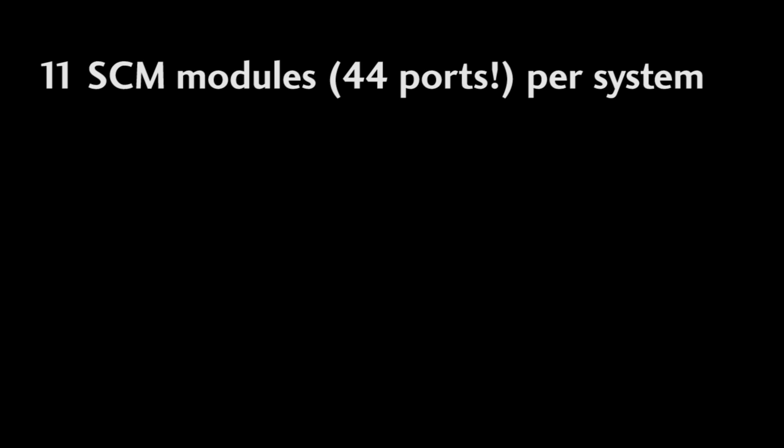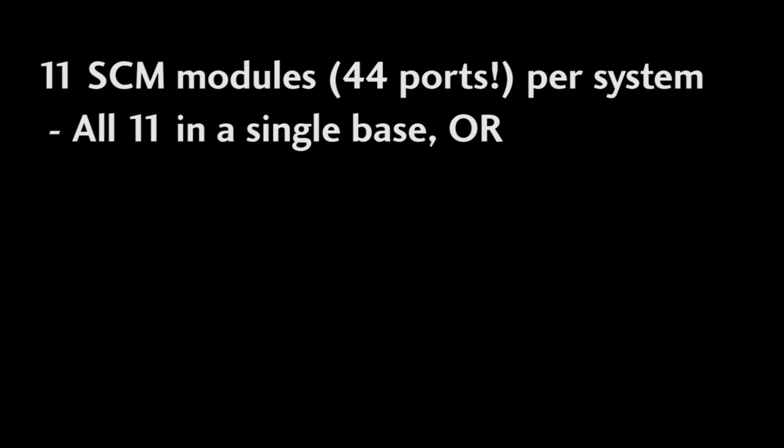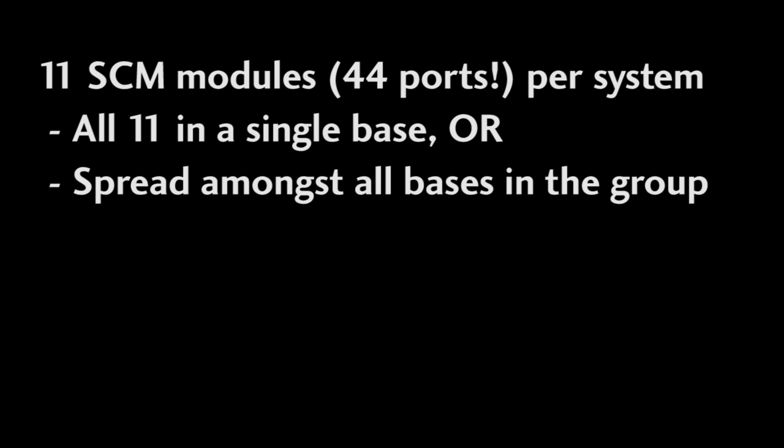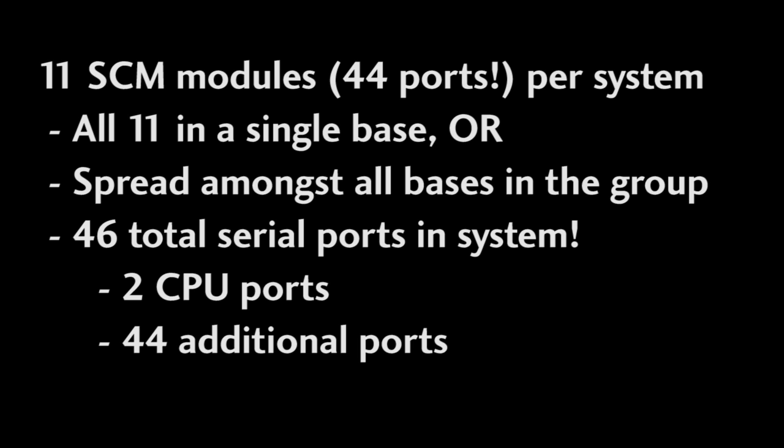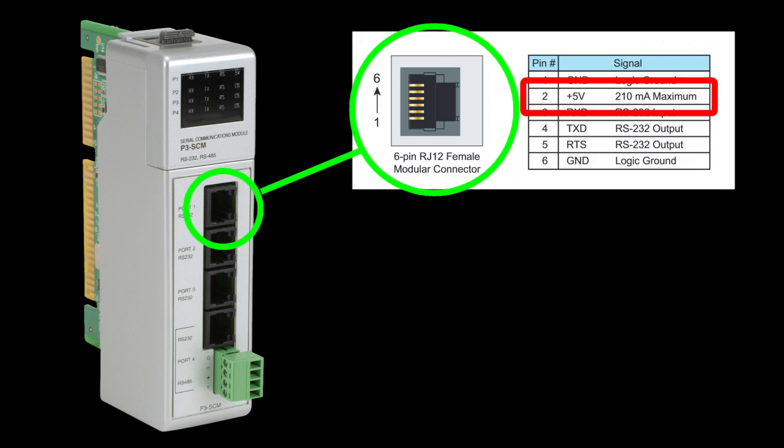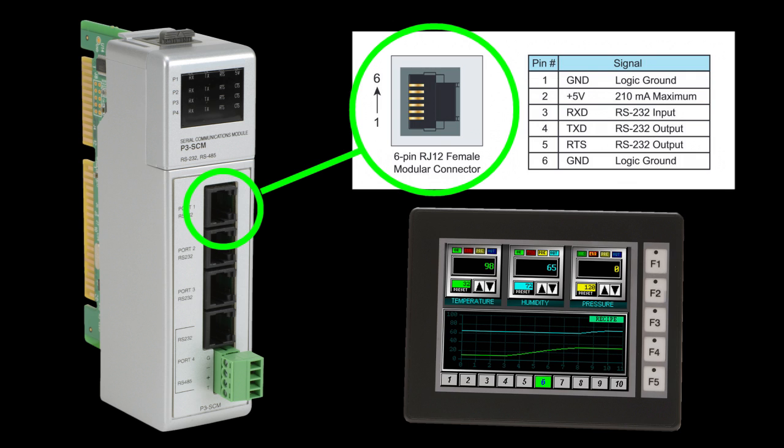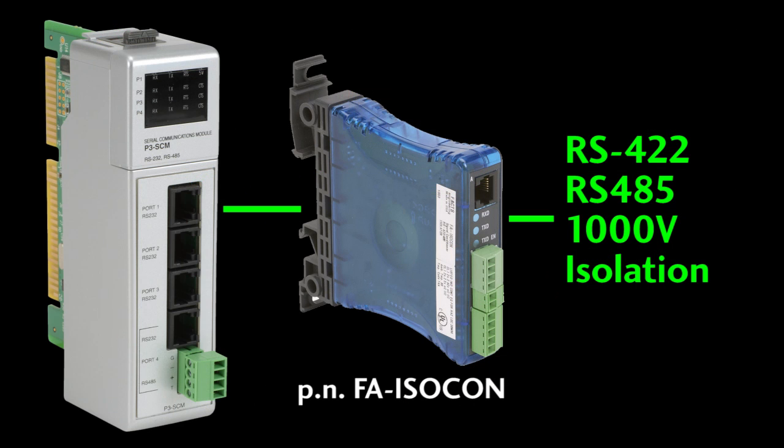A few notes. We already said that you can have 11 of these serial control modules in a system. That's all 11 modules in a single 11 slot base or spread out amongst remotes too. It's all exactly the same. That gives you 44 additional serial ports to use anywhere in your system. Remember, the CPU has an RS-232 and an RS-485 port built in so that's a total of 46 serial ports in a single system. The serial port 1 on the SCM supplies 5 volts on what would be the CTS pin. So now you can connect a C-more Micro directly to the port without an additional power supply. And you can create another 422 or 485 port by connecting the FA isocon. That gives you an extra 485 port with 1000 volts of isolation.